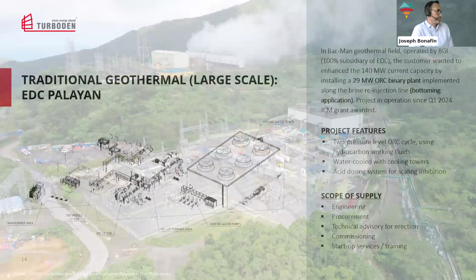Going to a few references: this is a large-scale project implemented in the Philippines, in operation since 2024, a water-cooled plant based on a traditional geothermal source. It's a 29 megawatt single generator combined with an existing single flash facility that was discharging hot brine to the reinjection line. We were awarded the repowering with this bottoming unit, which takes the brine before reinjection and returns it to the reinjection line. Here the complexity also involves dealing with high silica content, so we implemented an acid dosing system to avoid scaling of silicates.